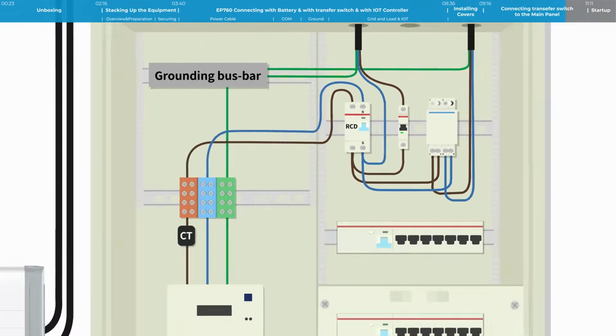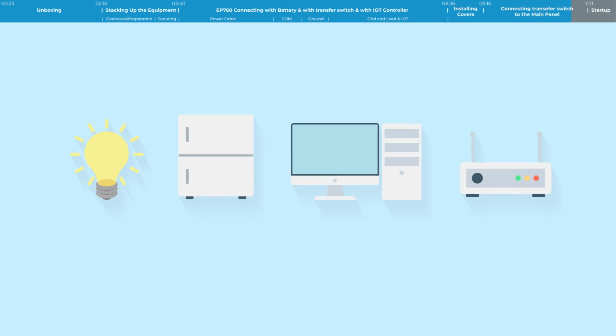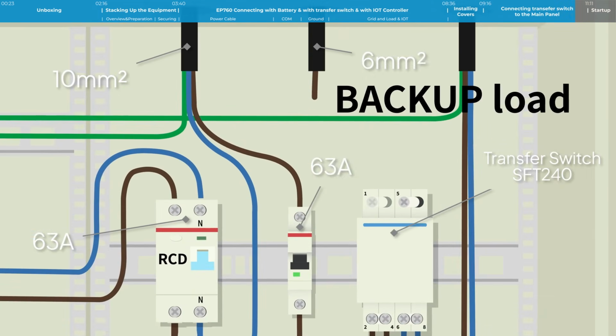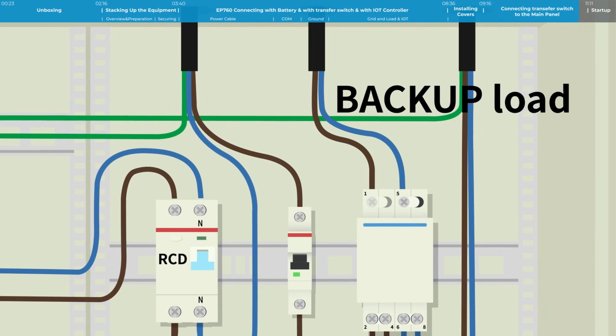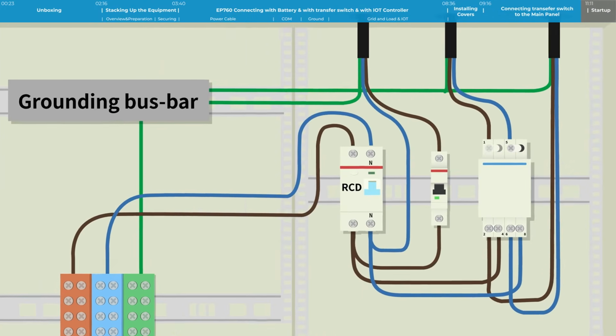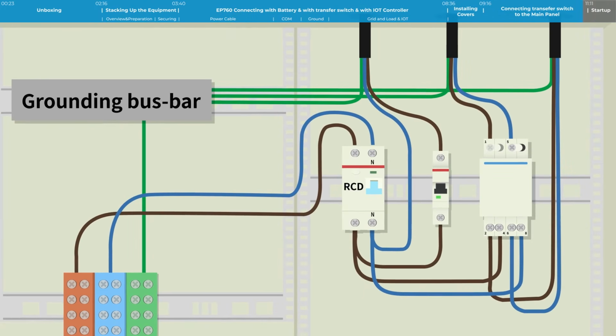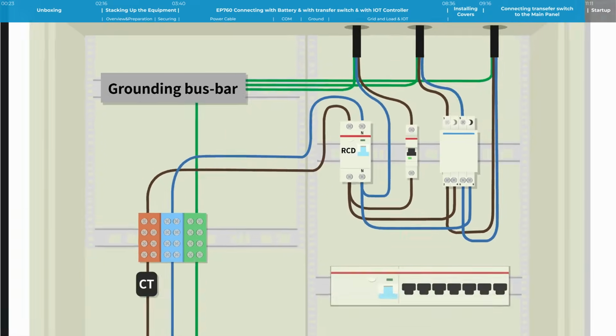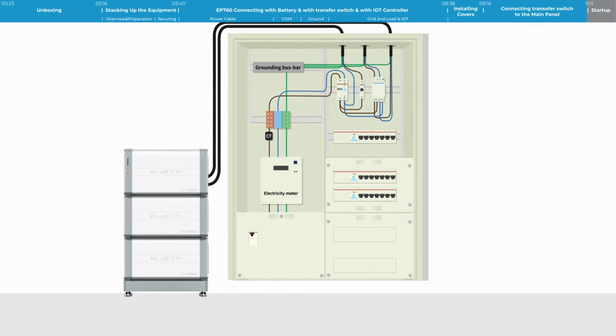Select some critical loads that need to operate during mains failure, e.g. lights, refrigerators, circuits supplying working computers or routers. Connect critical loads to the transfer switch, L to pin 1, N to pin 5. Please note that the total power of essential loads must be less than 7,600 W. That's all about connecting EP760 to the home distribution box.